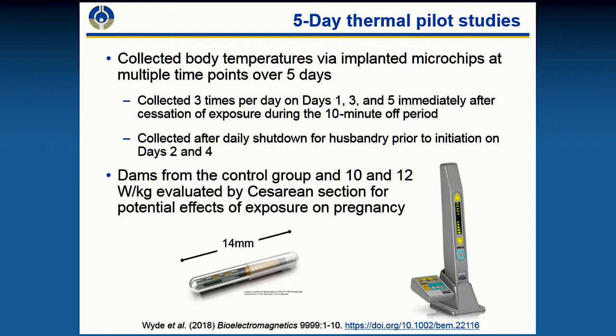So is this like an NFC or an RFID, or what's the frequency of communication? Because it's wireless, so I'm wondering. That I'm not sure, but I would have to go back and take a look. Okay. Although Miles might know because he's been working with some of this. Yeah, it's an RFID type system, so it's magnetic field. I think it's 120 kilohertz, something like that. So there's a little ferrite antenna, both in the sensor and in the wand. So the reader energizes briefly the transponder.